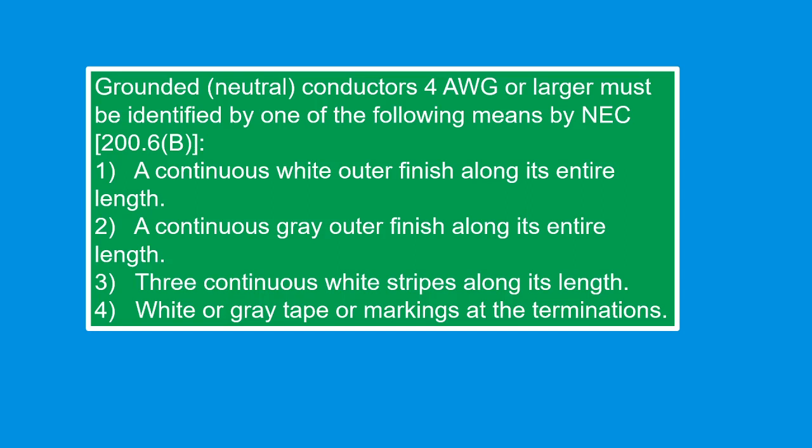Grounded conductors for American Wire Gauge 4 or larger must be identified by one of the following means per NEC 200.6B: Number 1, a continuous white outer finish along its entire length. Number 2, a continuous gray outer finish along its entire length. Number 3, three continuous white stripes along its length. Number 4, white or gray tape or markings at the termination.